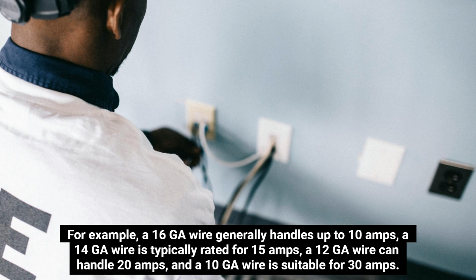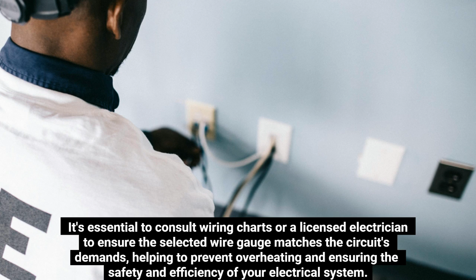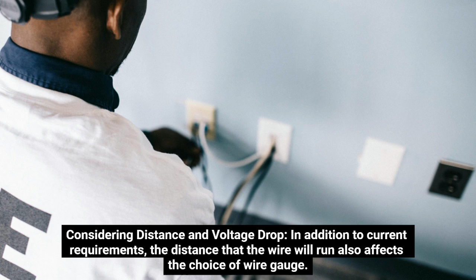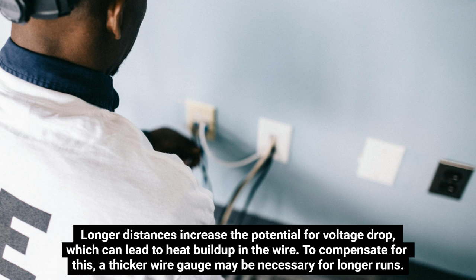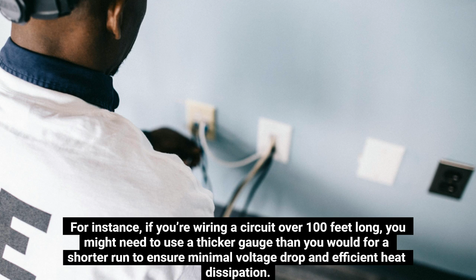It's essential to consult wiring charts or a licensed electrician to ensure the selected wire gauge matches the circuit's demands, helping to prevent overheating and ensuring the safety and efficiency of your electrical system. Considering distance and voltage drop. In addition to current requirements, the distance that the wire will run also affects the choice of wire gauge. Longer distances increase the potential for voltage drop, which can lead to heat buildup in the wire. To compensate for this, a thicker wire gauge may be necessary for longer runs. For instance, if you're wiring a circuit over 100 feet long, you might need to use a thicker gauge than you would for a shorter run to ensure minimal voltage drop and efficient heat dissipation.